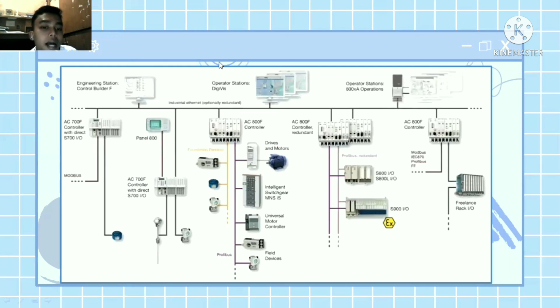First, sensors sense the process information and send it to the local input and output module, to which actuators are also connected so as to control the process parameters. Then the information or data from this remote module is gathered at the process control unit via the field bus.